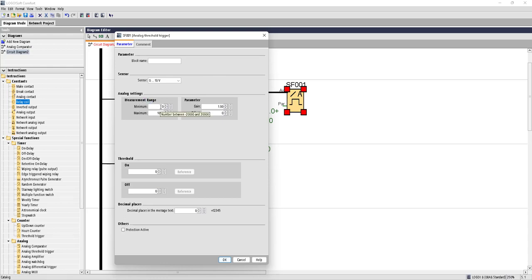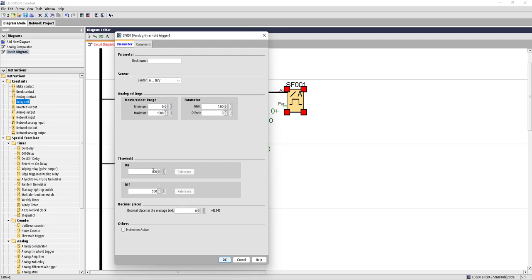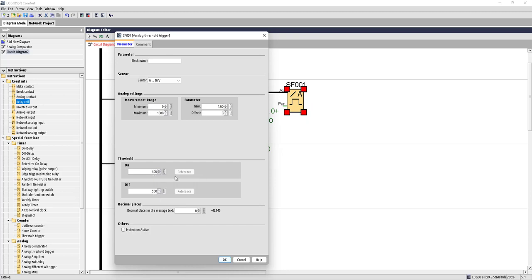Now you can choose the values or the range here of measurement. Suppose it's a sensor that's measuring between 0 and 1000, and you want to give it a threshold of 400 to 500. So whenever the sensor value reaches in between this limit of 400 to 500, it will turn on the output. And whenever it goes beyond or ahead of this value limits, it will turn off the output load.